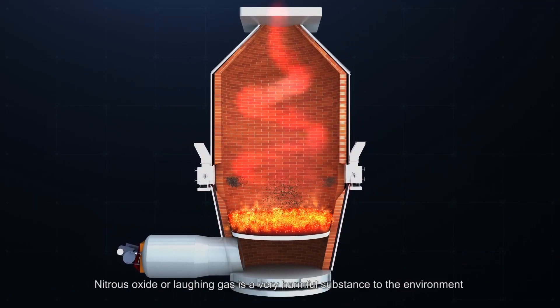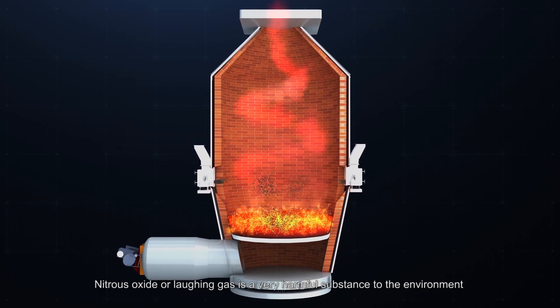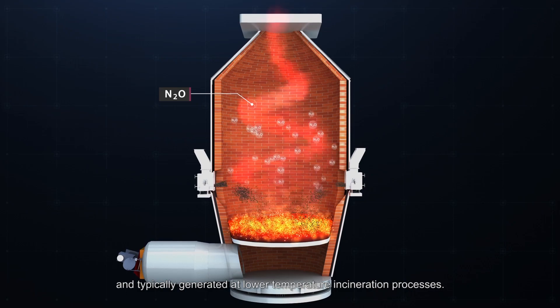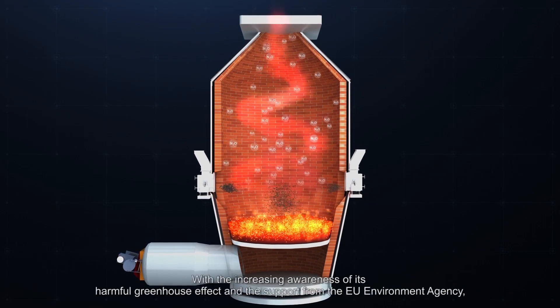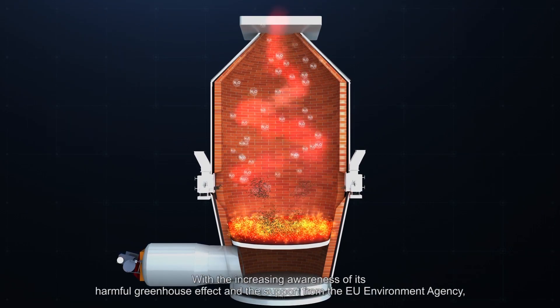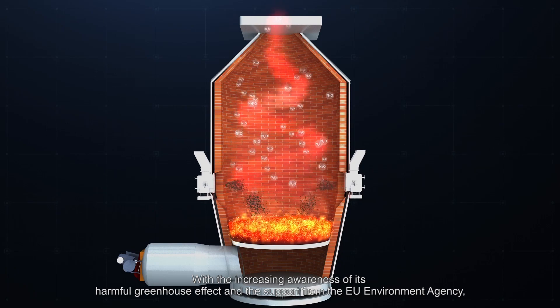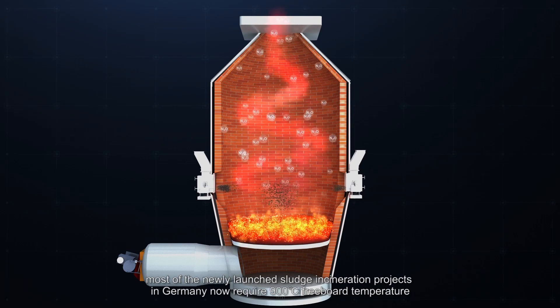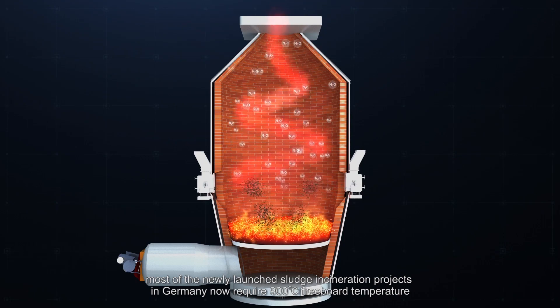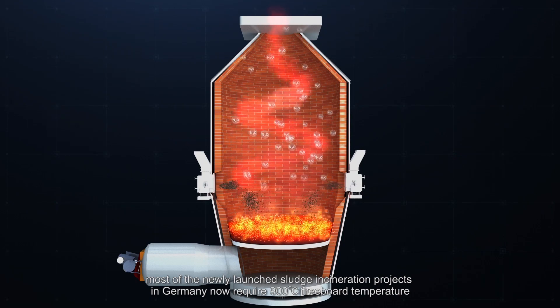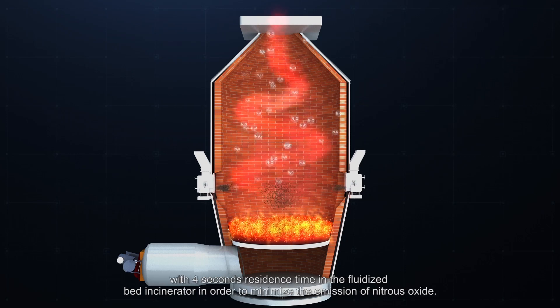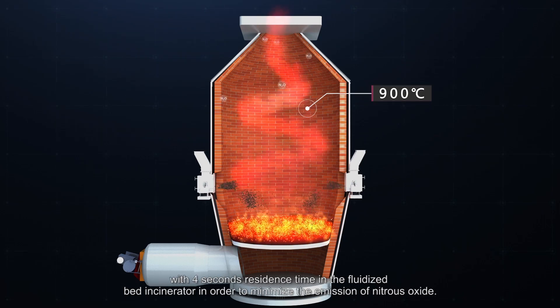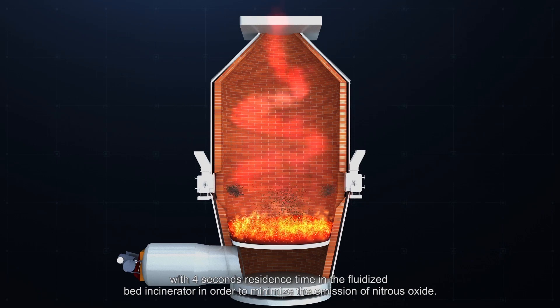Nitrous oxide, or laughing gas, is a very harmful substance to the environment and typically generated at lower temperature incineration processes. With the increasing awareness of its harmful greenhouse gas effect and the support from the EU Environment Agency, most of the newly launched sludge incinerators projects in Germany now require 900 degrees Celsius freeboard temperature, with four seconds residence time in the fluidized bed incinerator in order to minimize the emission of nitrous oxide.